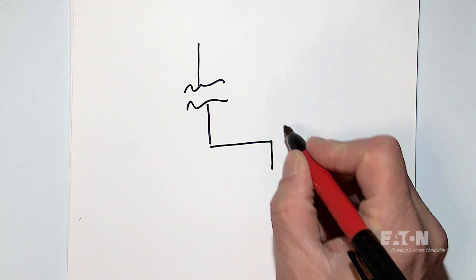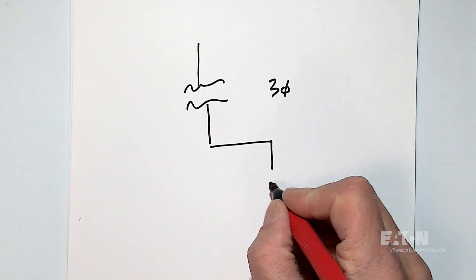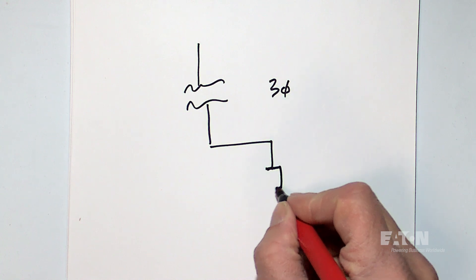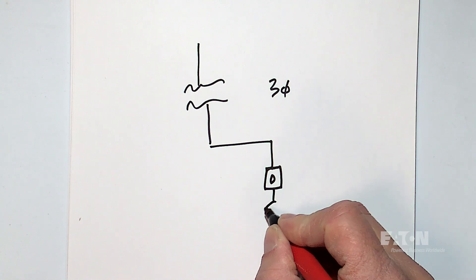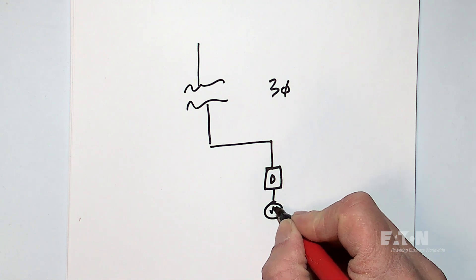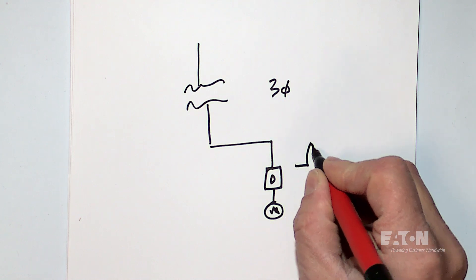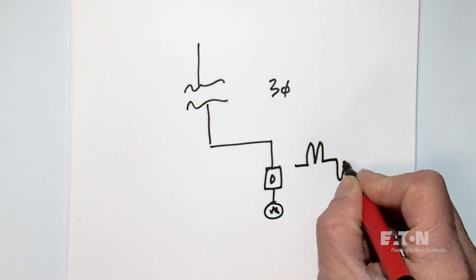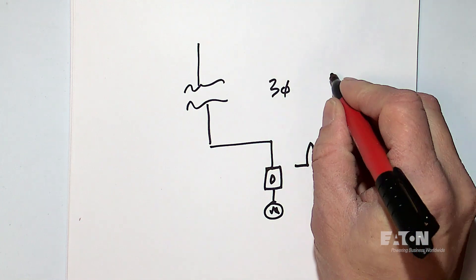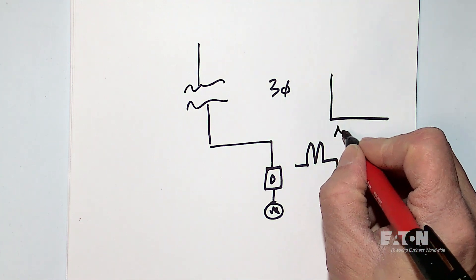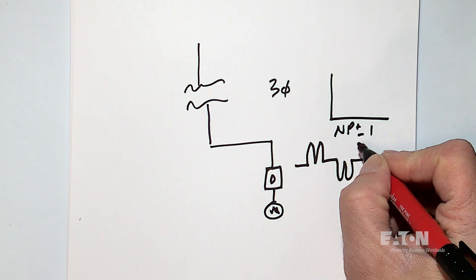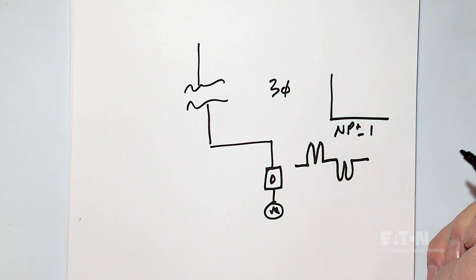So on a three phase system, if I have a drive and I have a motor, my harmonics current is going to look something like this. Again, very characteristic. I'm going to have a spectrum that looks like NP plus or minus one, where P is the number of pulses, N is just an integer—one, two, three, four, five—plus or minus one.